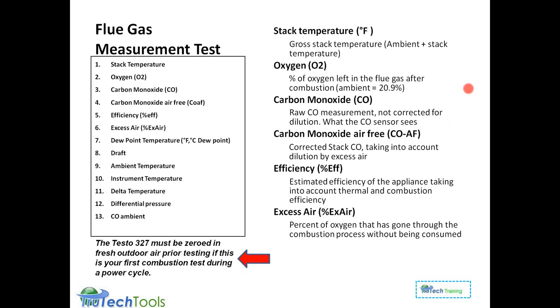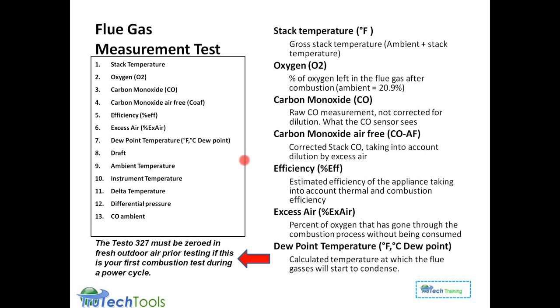Okay. Dew point temperature is a calculated temperature at which the flue gases start to condense. We talked about that before. It's one number for each different type of fuel. But you can bring it up on the screen if you're interested in seeing what your current stack gas temperature is compared to the dew point temperature. You'll know if condensation could be happening around the point that you're taking that measurement.